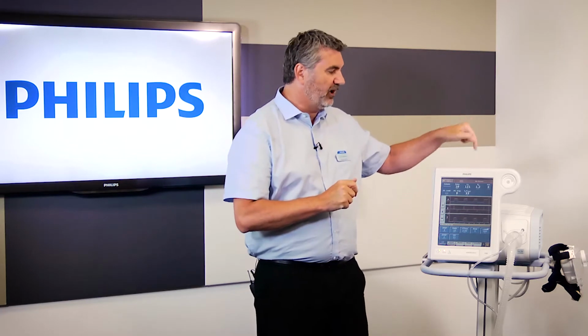about the technology. So, as we've said, called the V60, it's the new version of the BiPAP Vision, so some of you may have those. And what it is, it has its own internal blower. It's a very, very high flow blower. It can do 200 up to about 260 litres of flow can be generated from this device. So there's no need to put a separate air supply into this machine.